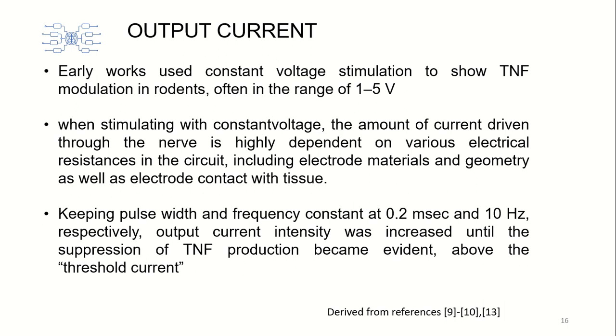To translate the early discoveries into a consistent therapy, we first methodically investigated a range of constant current stimulus parameters in rodents. Keeping pulse width and frequency constant at 0.2 millisecond and 10 Hz respectively, output current intensity was increased until the suppression of LPS-induced TNF production became evident above the threshold current. The empirically established threshold current ranged from 0.25 to 0.50 milliampere for mice and from 0.10 to 0.25 milliampere for rats.